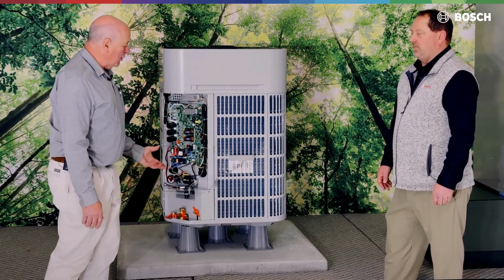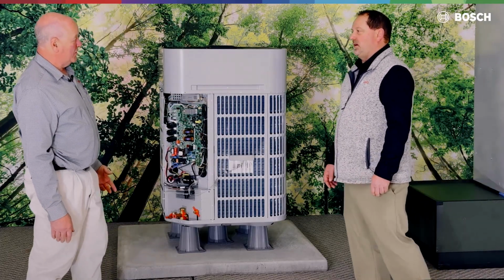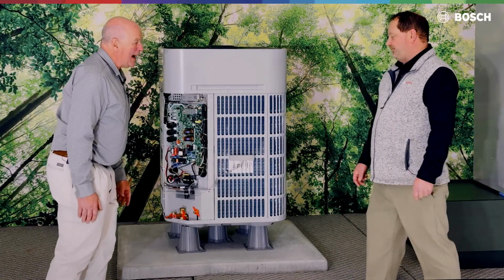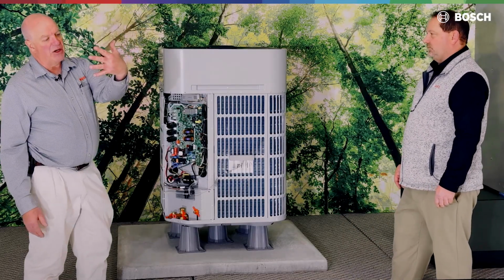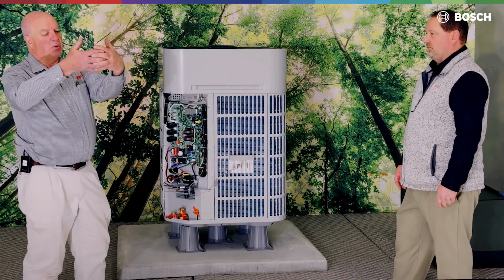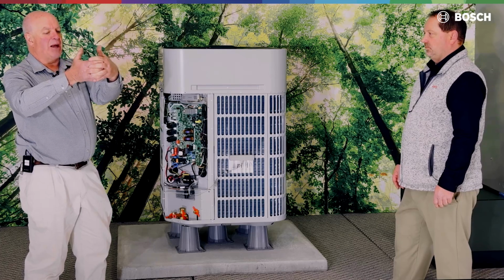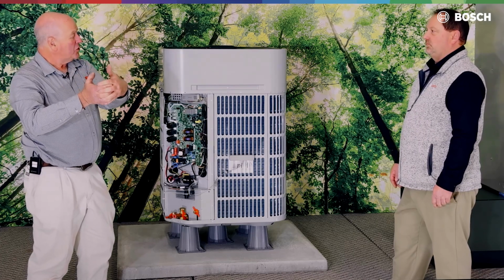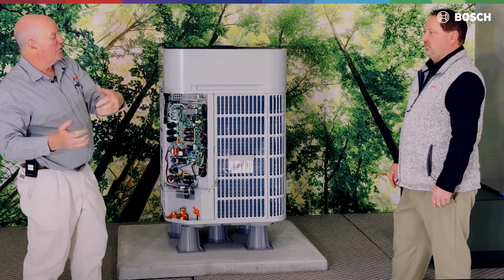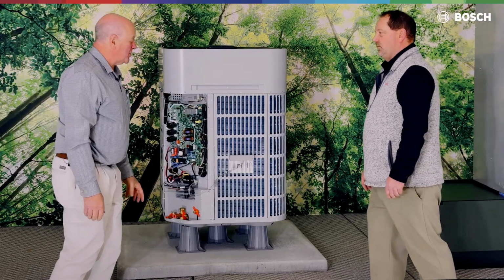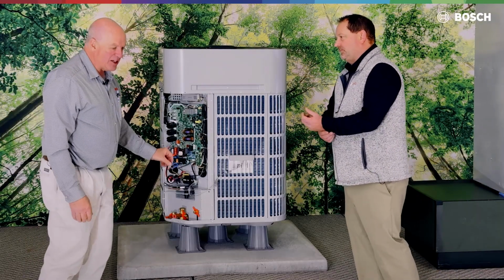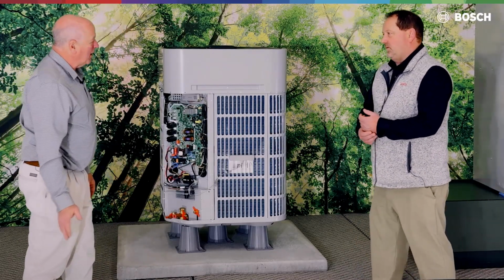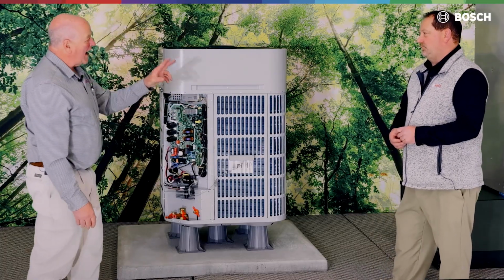What happens with moisture in a vacuum is it turns to ice. Yes, sir. And if we don't get that ice back out of there, our POE oil mixing with the refrigerant forms a white wax. It gets between the superheat spring and my TXVs don't respond. So we're going to be a little forceful on getting the moisture out of our system. We put that nitrogen in, let it sit for 5 minutes. At the end of 5 minutes, we're going to bring on a vacuum pump and pull vacuum number 2.